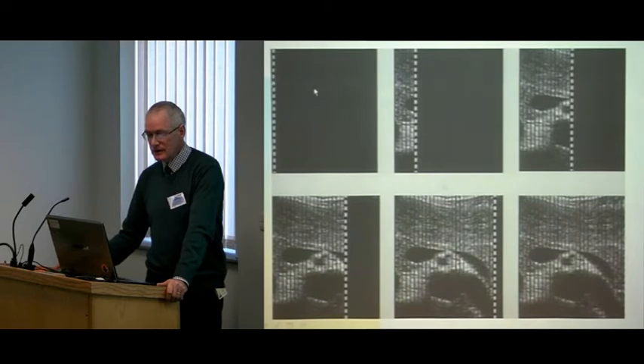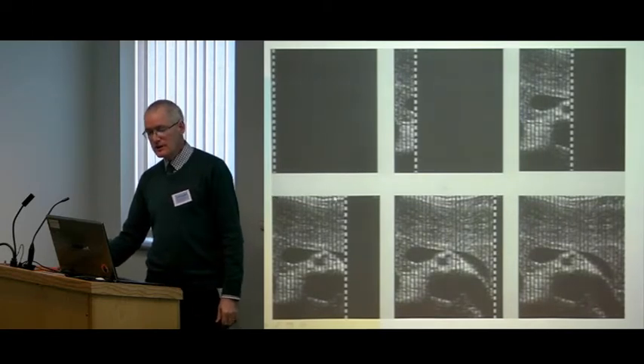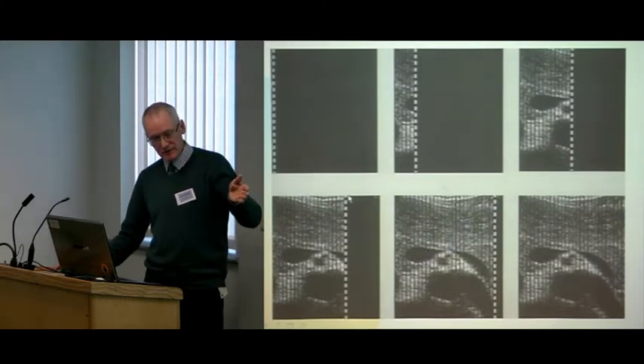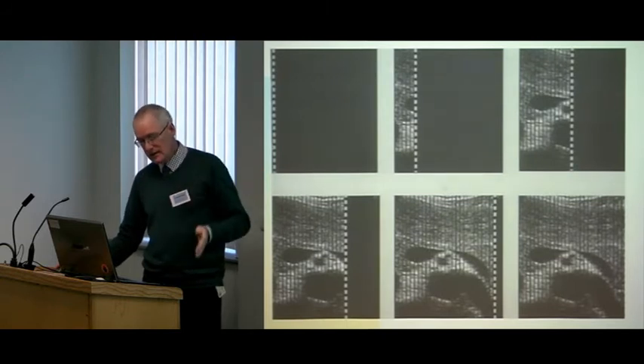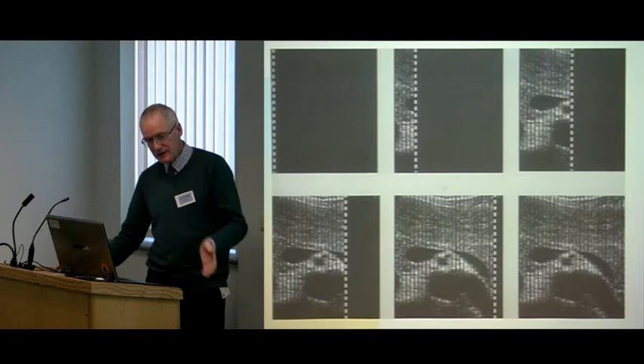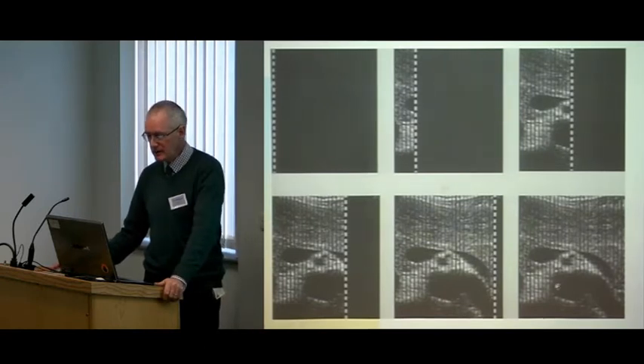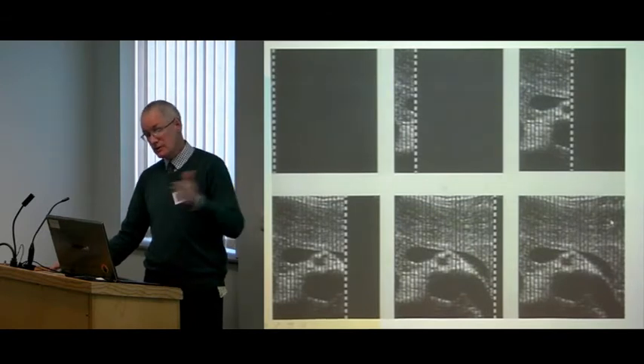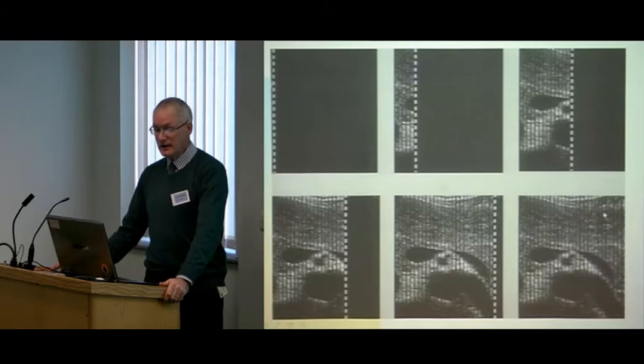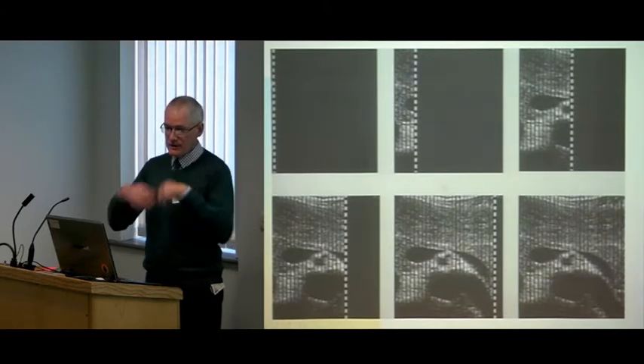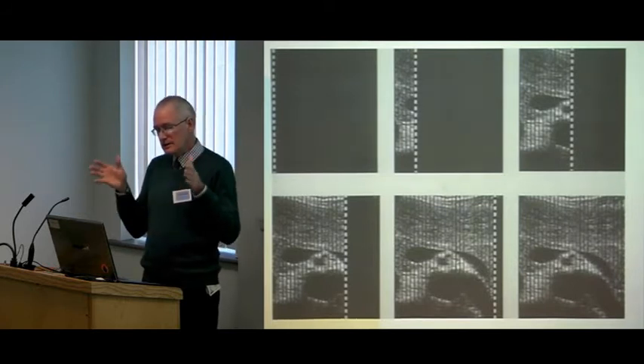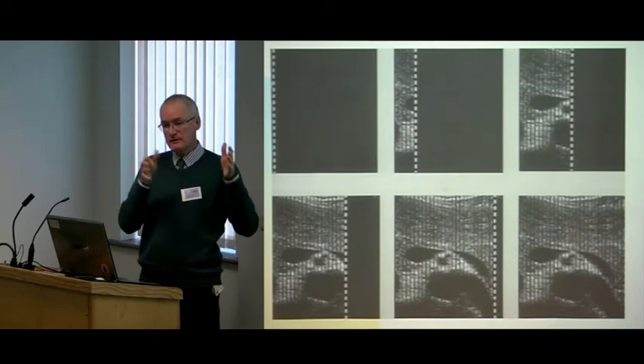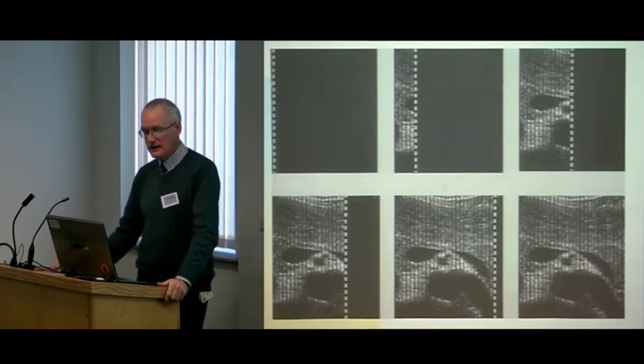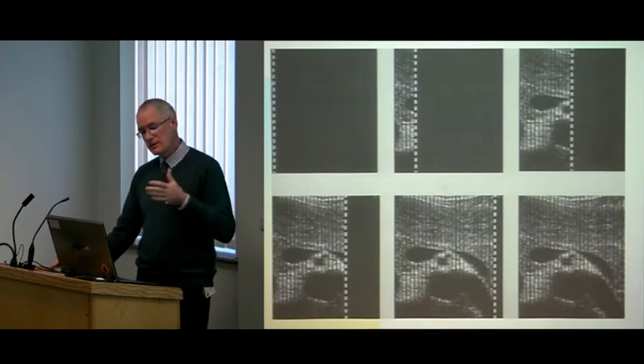If we were to look at the image that's produced on your screen, you will see that the image is produced in a raster fashion, in that there is a series of pulses that come across the probe like this, and the reflections that come up from the different times, depth and distance along the image are built up in a format that looks like this, but so fast you can't really appreciate it to the eye, unless the screen refresh rate, the judder effect on the screen, is so slow that you can see movement of the image very slowly like this if you have lots and lots of software activated at the same time. So the frame rate refresh is something that you've got to be considering in order to allow you to move the probe without judder on the patient's skin.